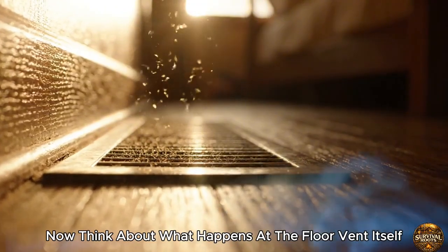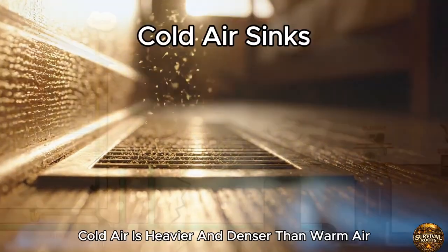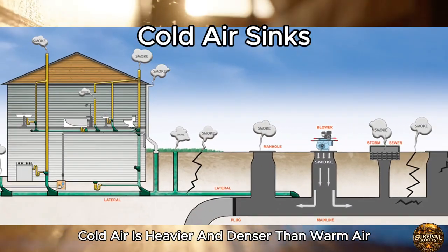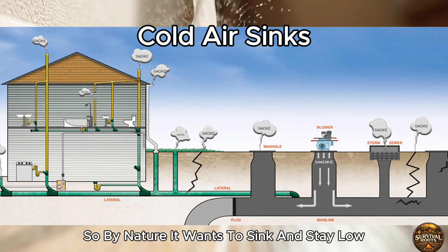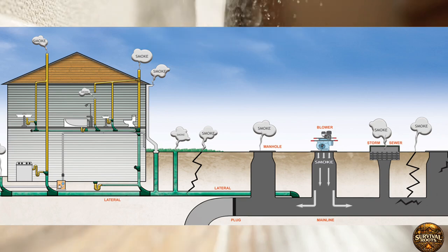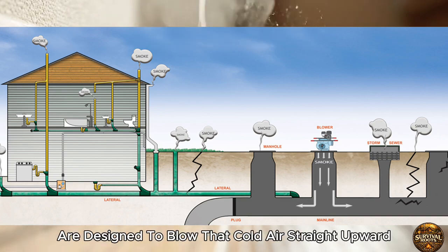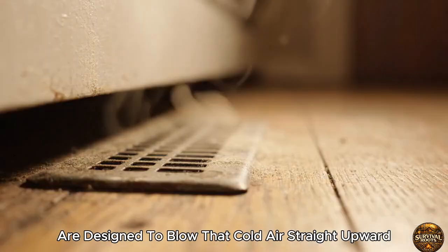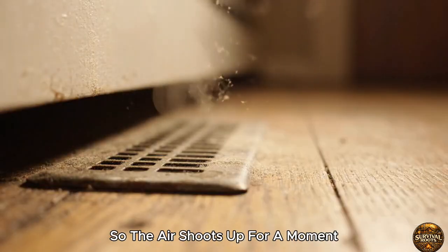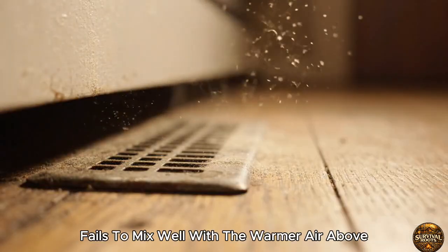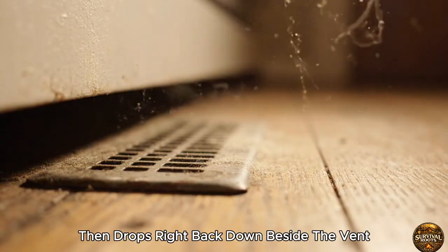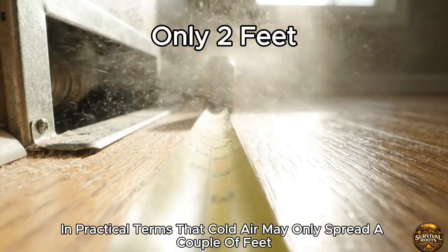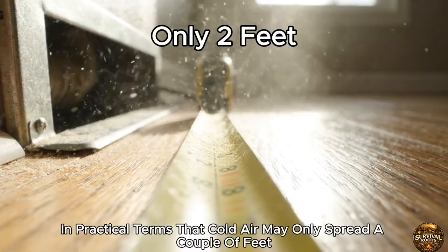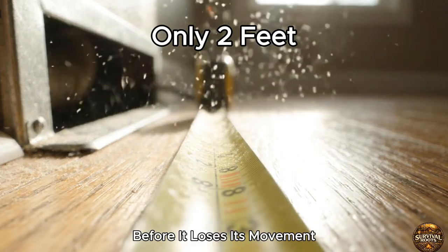Now think about what happens at the floor vent itself. Cold air is heavier and denser than warm air, so by nature, it wants to sink and stay low. But most standard floor registers are designed to blow that cold air straight upward, so the air shoots up for a moment, fails to mix well with the warmer air above, then drops right back down beside the vent.